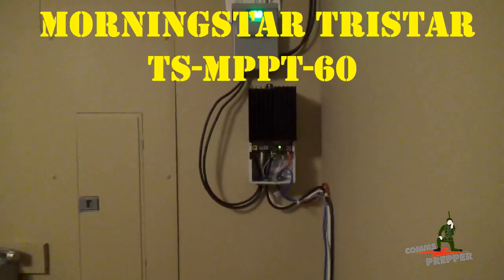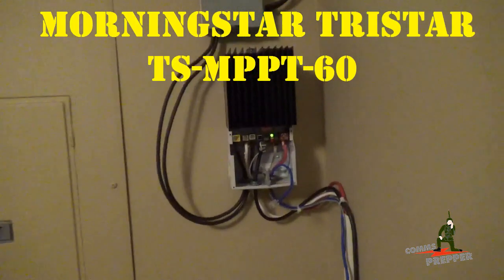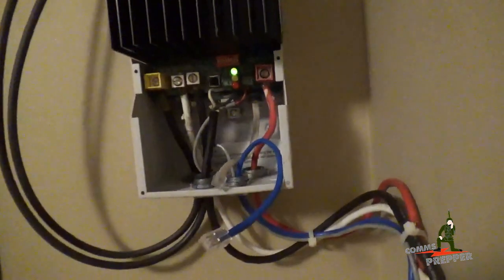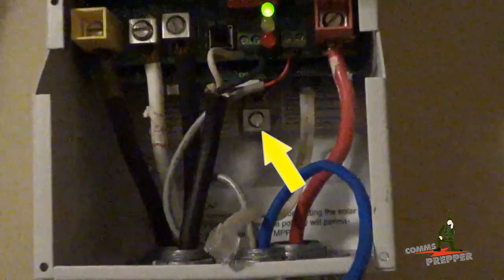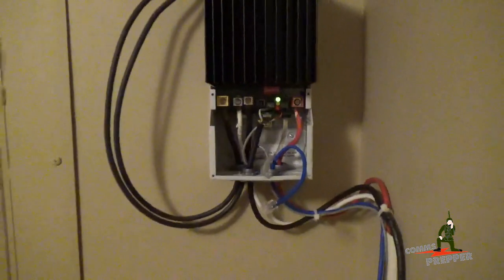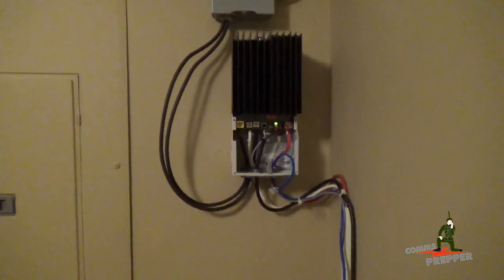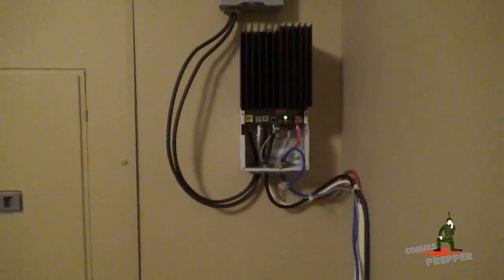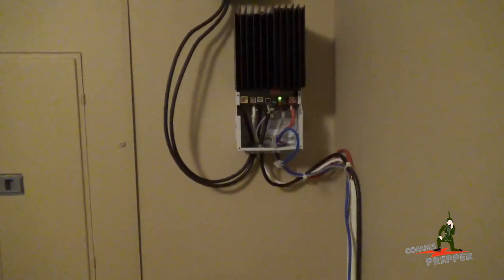Here I have my Morningstar TS-MPPT-60 charge controller, and in the back there — if you can see — that is a ground post, and I never quite did finish this project up. So today we're going to ground this system out to our external ground rod. We'll bring the inverter over, ground it, and then run ground wire up to the individual panels, putting everything on a common ground going to the ground rod for the house.